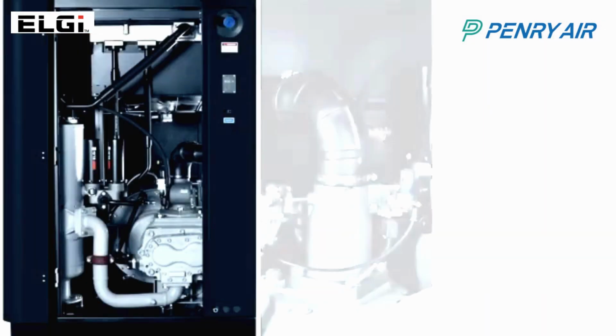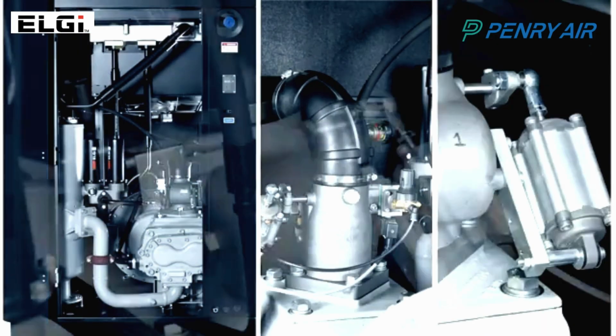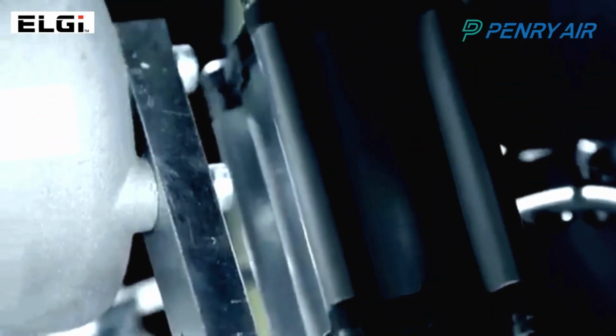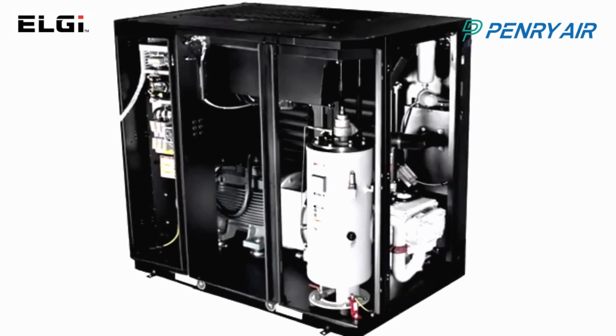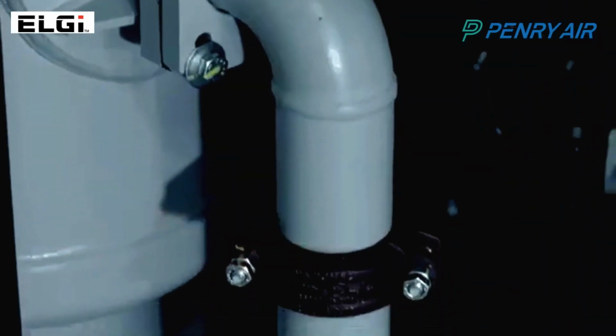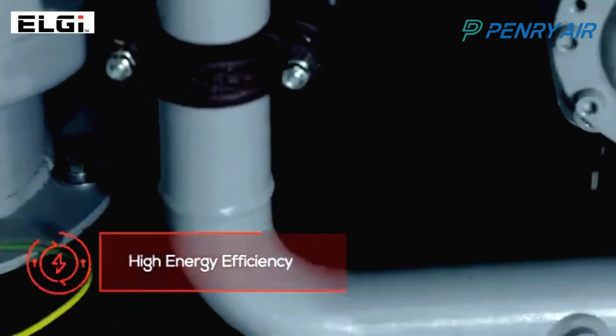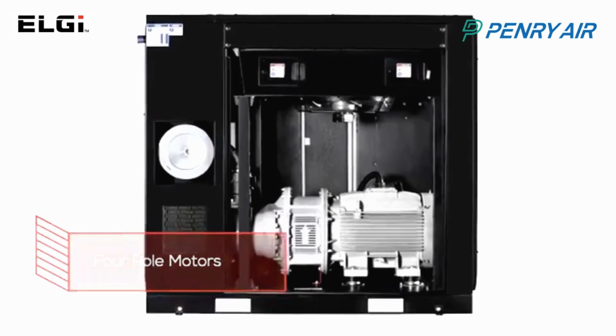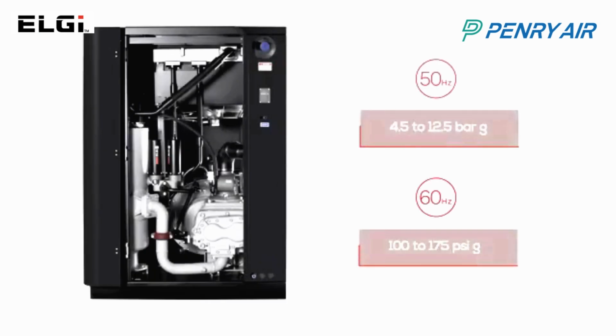The intake valves offer suction modulation that saves 20% of energy during the load and unload cycles. The compressor subsystems are designed to minimize pressure losses and ensure high energy efficiency. The 4-pole motors have been designed to be more efficient than 2-pole motors. The pressure versions enable customers to select the optimum variant for their application.